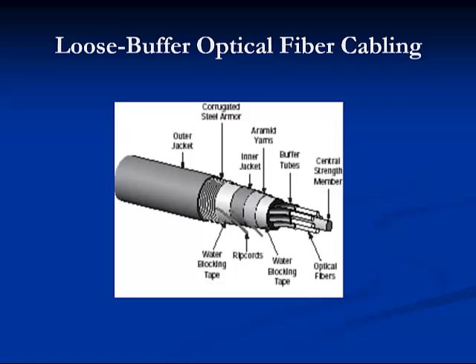A loose tube buffer is essentially a tough plastic pipe about an eighth of an inch in diameter. One or several coated fibers can be placed inside the tube, which is then filled with a protective substance — usually a water blocking gel — to provide cushioning, strength, and protection from the elements. Water block powders and tapes may also be used. A loose tube design is commonly used in outdoor installations, and multiple tubes can be placed in a cable to accommodate large fiber counts for high density communication areas such as large cities or long distance trunk lines.